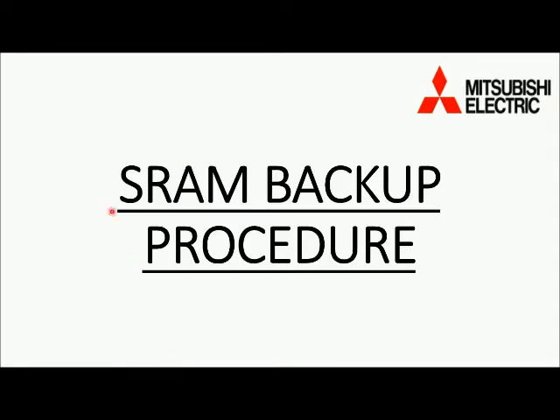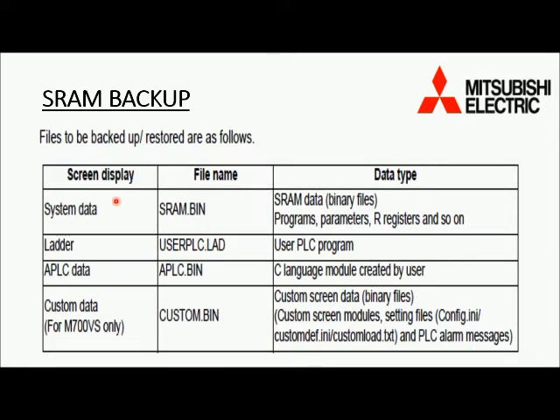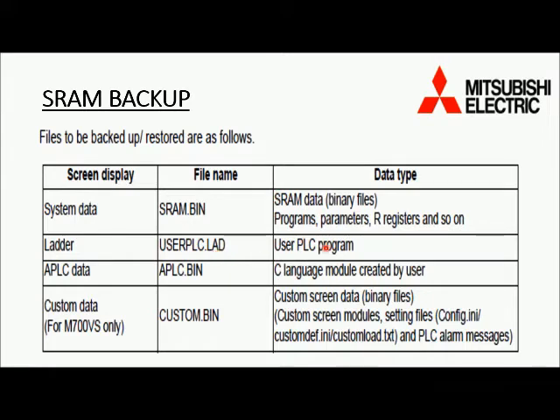Now we will explain about SRAM backup and how to take it. In SRAM backup there are several types of data. The first is system data, which comes in the SRAM.bin file — this file saves SRAM data in binary format, including programs, parameters, registers, and so on. The second is ladder, which comes in the USERPLC.LAD file and contains the ladder or PLC of the machine.